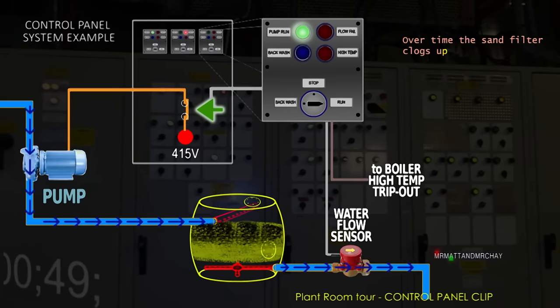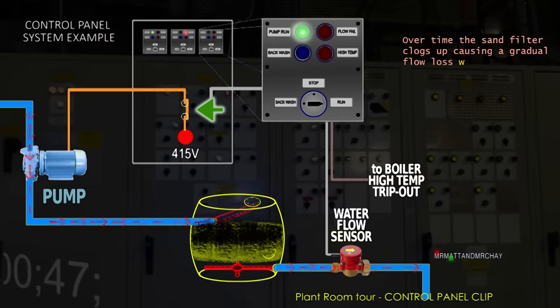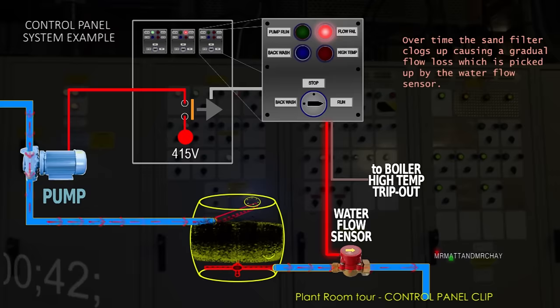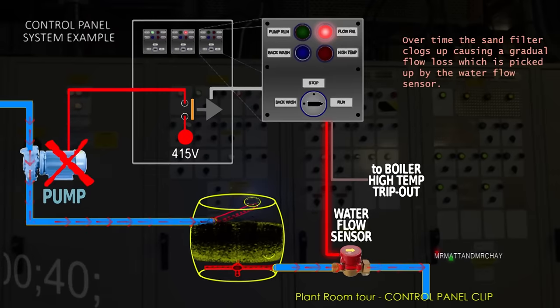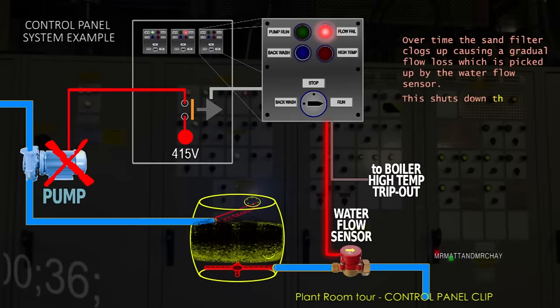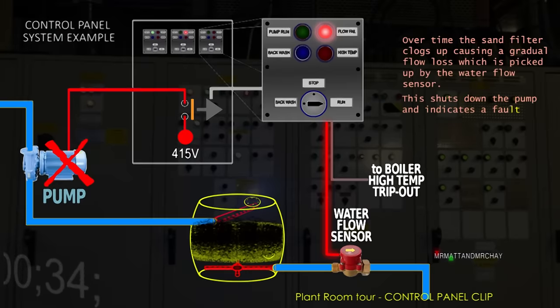Over time the sand filter clogs up with dirt particles in the water, which causes a gradual flow loss. This is picked up by the water flow sensor, which now signals a fault to the control panel. Inside the cabinet the motor is shut down and shows a fault on the panel.